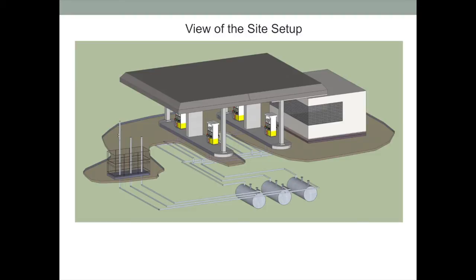The actual configuration at the site is pretty close to what the site actually looked like. The tanks themselves have vent lines that run to the vent stacks. They also have liquid lines with a check valve at the bottom that run to the dispensers at the site. The only open part of the system is really just the vent line. The fill ports on the tanks are normally closed during normal operation and are only opened up briefly when the tank truck comes to the site and connects.